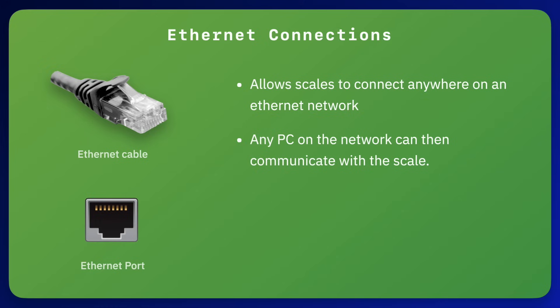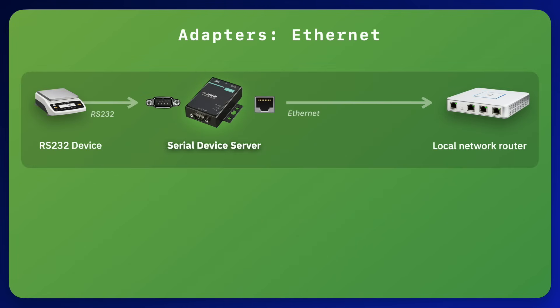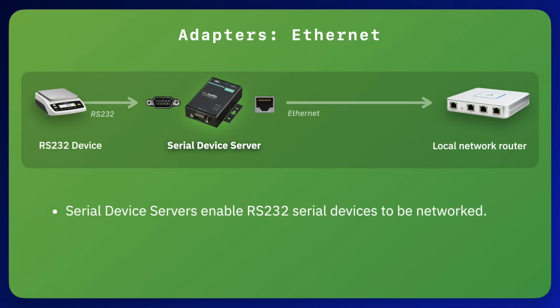If you have a scale that has an RS-232 connector and you would like to connect it to your network, you can convert it to an Ethernet network connection using a device called a serial device server. A serial device server has an RS-232 port on one side and an Ethernet connector on the other.